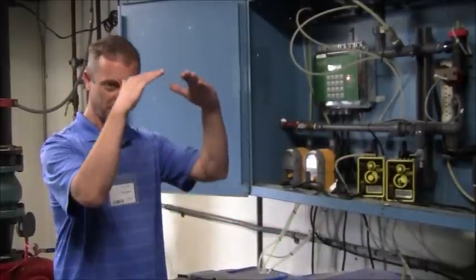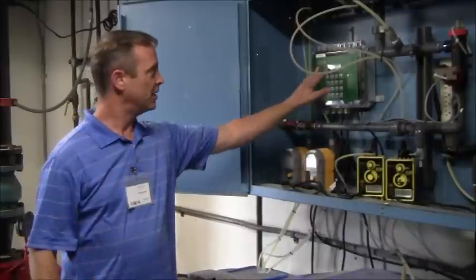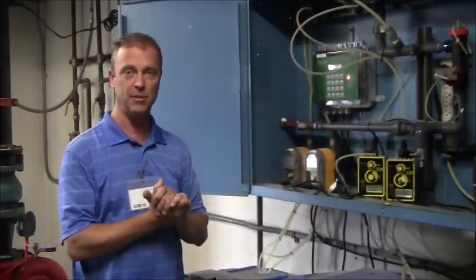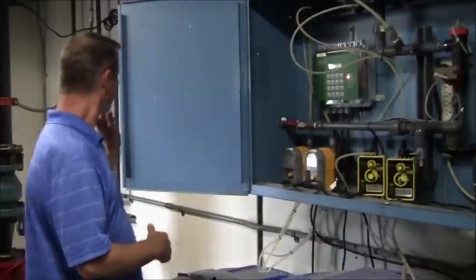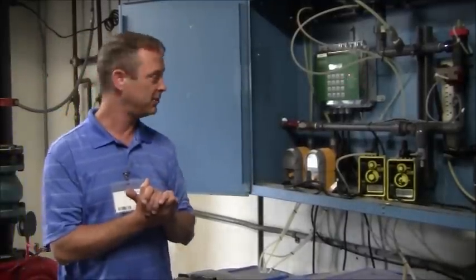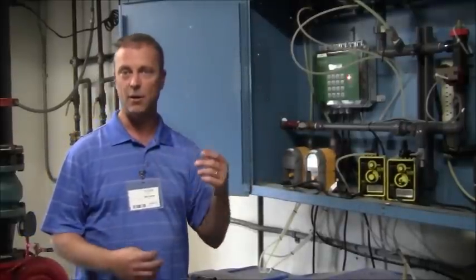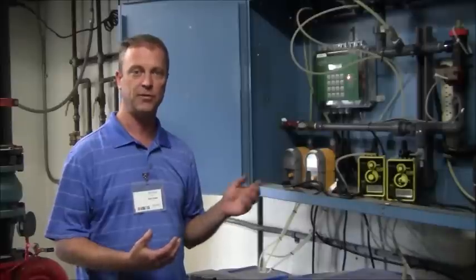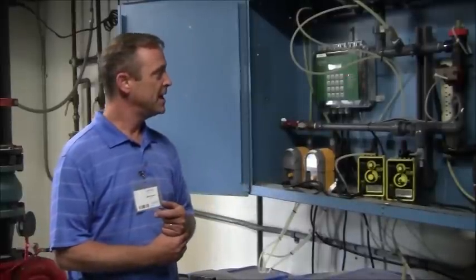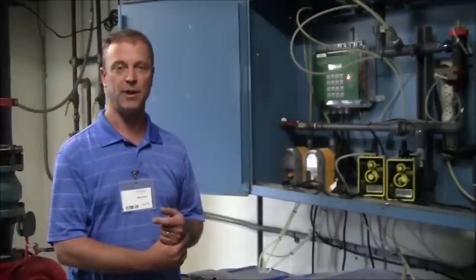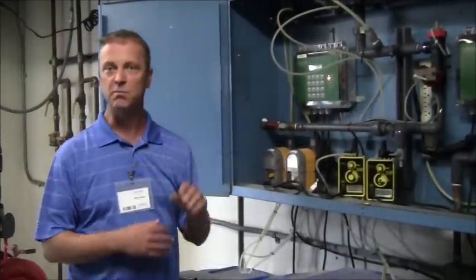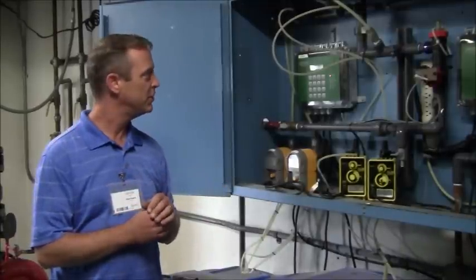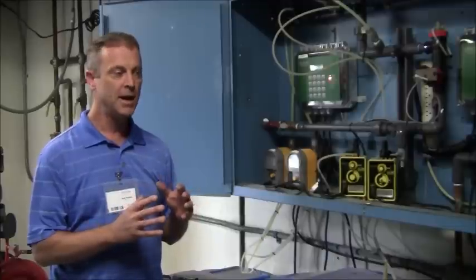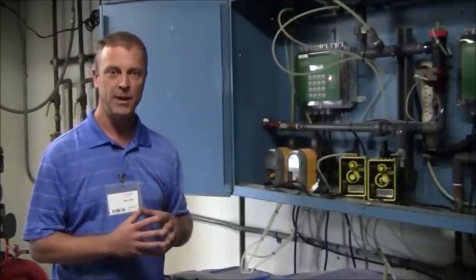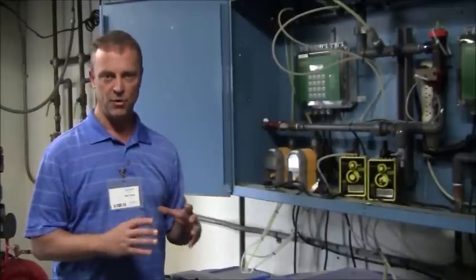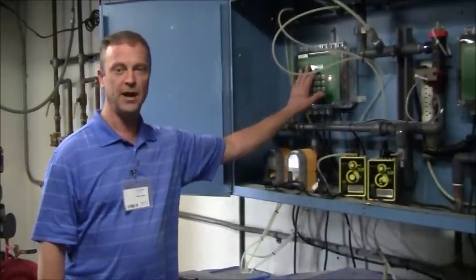It all mixes and blends. It brings the conductivity back under control. And the controller senses that and says, okay, now it's time to shut the bleed valve. The bleed valve will shut. It'll disconnect the power to the bleed and stop that process. And then the inhibitor gets fed back into the tower because we've lost a little bit of treatment through that process, and so we'll feed it back into the system at that point. And that's basically the nuts and bolts of this operation. You know, we try and keep the probe clean. We take care of that, pulling that probe out once in a blue moon and making sure we keep it clean so it's tracking accurately. And then you always want to really do your bench testing with your bench testing equipment so that you can make sure that this controller is reading accurately as well.